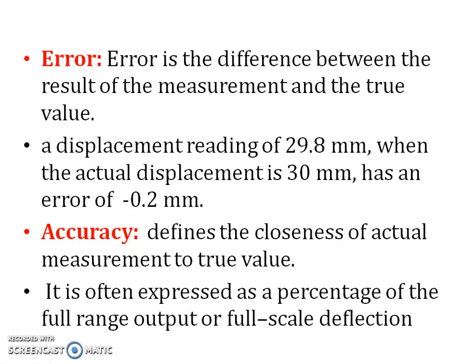Error is the difference between the result of the measurement and the true value. A displacement reading of 29.8 mm when the actual displacement is 30 mm has an error of minus 0.2 mm. Accuracy defines the closeness of the actual measurement to the true value. It is expressed as a percentage of the full range output or full scale deflection.